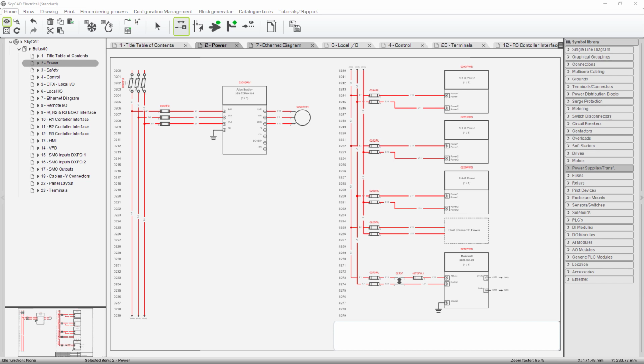And the reason that they use high voltage is because the higher the voltage, the lower the current. Volt amps, volt amperes, power, watts, volts times amp. 480 at 1 amp is 480 watts. 120 at 4 amps is 480 watts. But it takes more copper to conduct 4 amps than it does 1 amp. Now I'm using just some real simple numbers. That's why they use high tension lines, because the higher the voltage, the lower the current to get the same power. So you can use smaller conductors, less expensive.